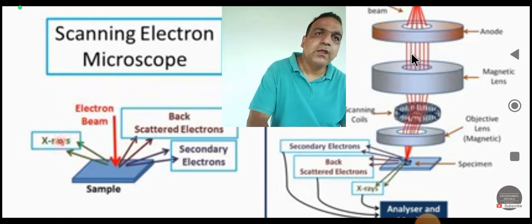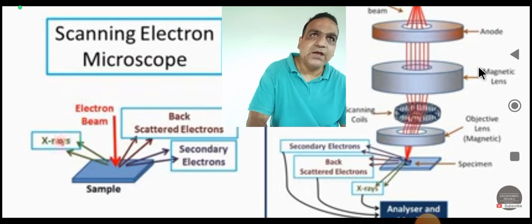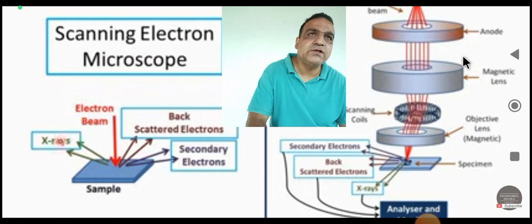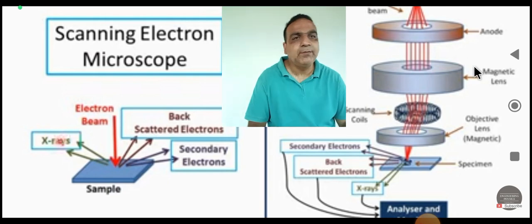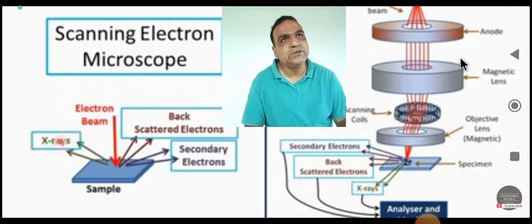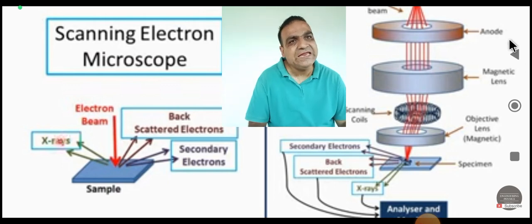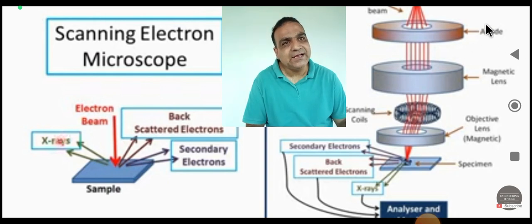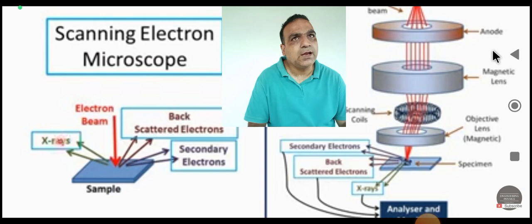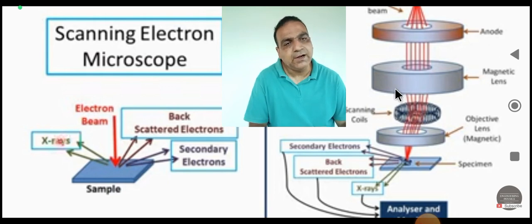So this scanning electron microscope is a powerful imaging instrument that uses electron beam to examine the surface of the sample in high detail. It provides a three-dimensional view of the sample surface by scanning a focused electron beam across the specimen and detecting the emitted signal. Here's an overview of the working of an electron microscope.